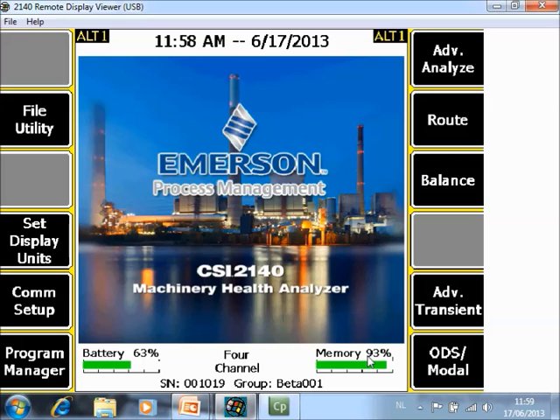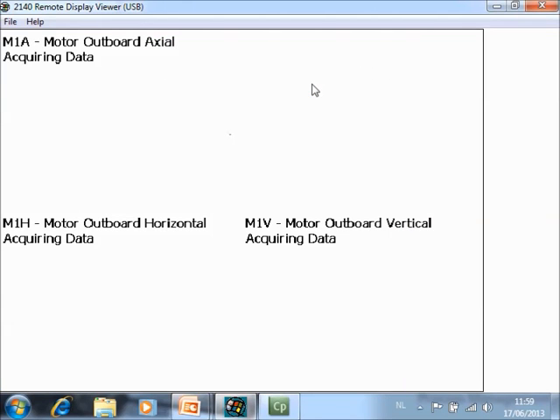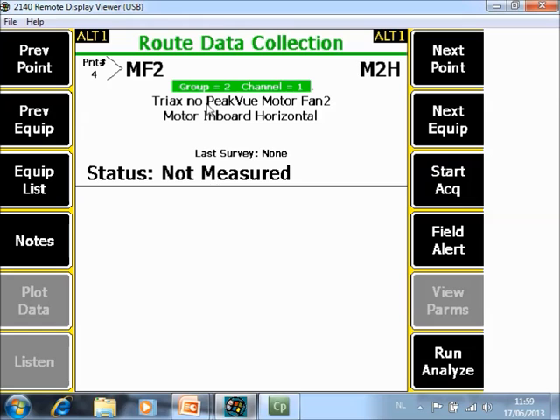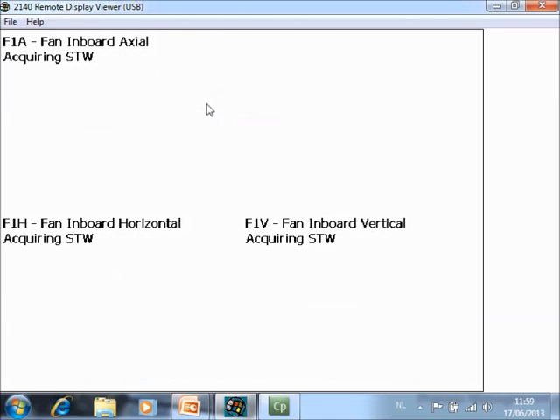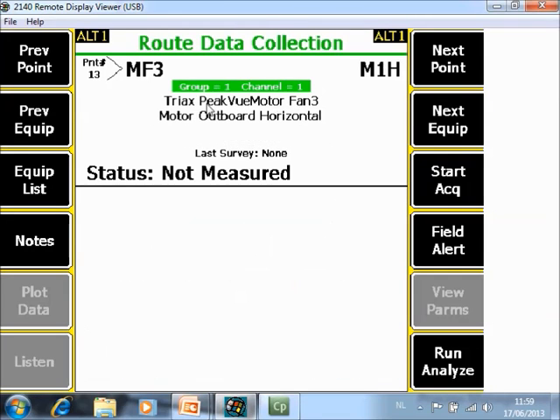I will start the machine — you may hear some additional noise — and on the home screen of the analyzer I go to Route Mode. Now I am in the first machine and we are at motor outboard horizontal, which is grouped. When I push enter, you will see it taking horizontal, vertical, and axial motor outboard simultaneously. After finishing that it jumps automatically to the inboard, where I collect data, measuring horizontal, vertical, and axial simultaneously. It then jumps to the fan, starts measuring and collects the three measurements simultaneously, and finally the last plane, fan outboard. The complete machine is done.